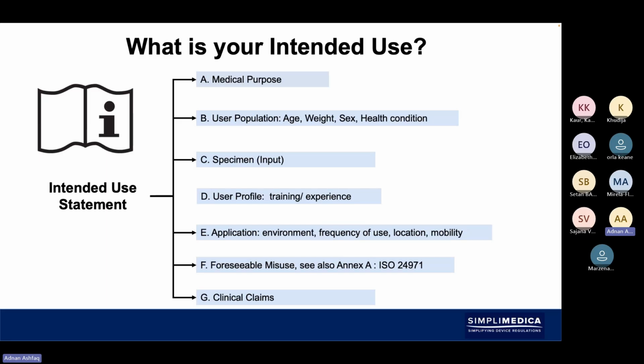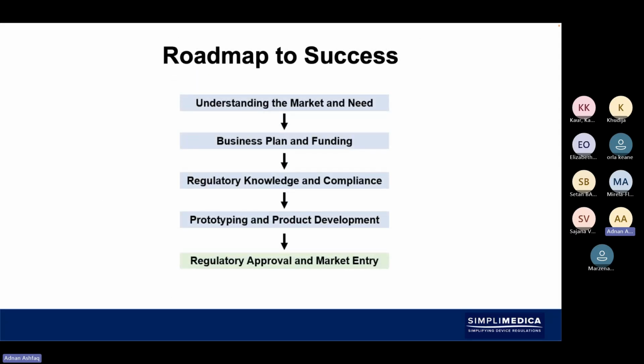And then what foreseeable misuse? What's the worst thing that could go wrong? Are we looking at death by misuse of the device, or are we looking at possibly just some inconvenience or trauma, anxiety, stress, those types of things? Annex A of ISO 24971 will also help you in the intended use statement. There's a series of questions asked about the characteristics of the device, which will then help you formulate this intended use statement. And then last but not least, the clinical claims. What claims are you making that make your device a medical device? Because anything that fits the definition of a medical device will have a clinical benefit and will have some form of claims that you are looking to make, and those then need to be validated. So this is all very, very important. This is really looking at the foundations and the basic form of what the medical device journey is going to look like.